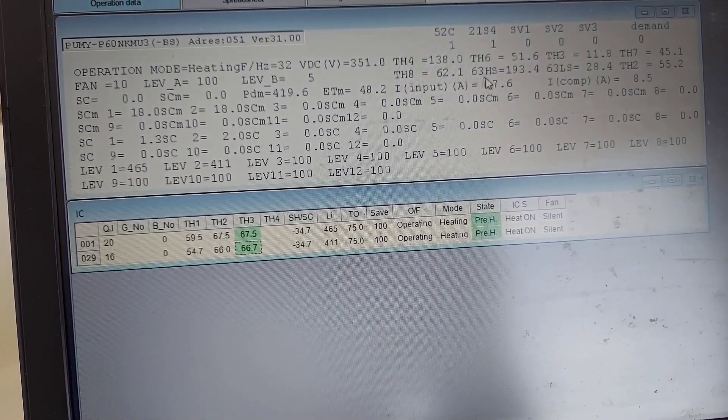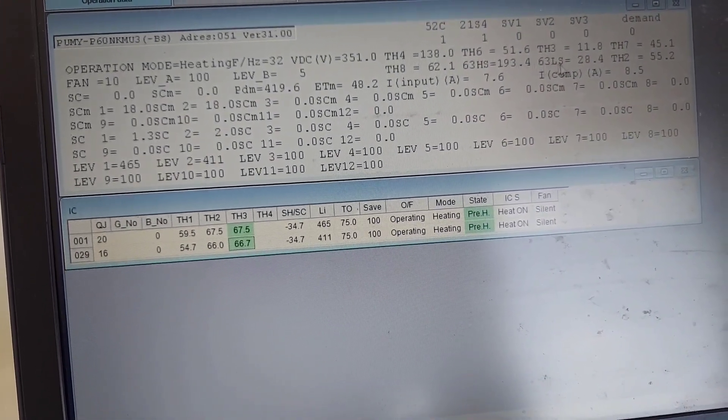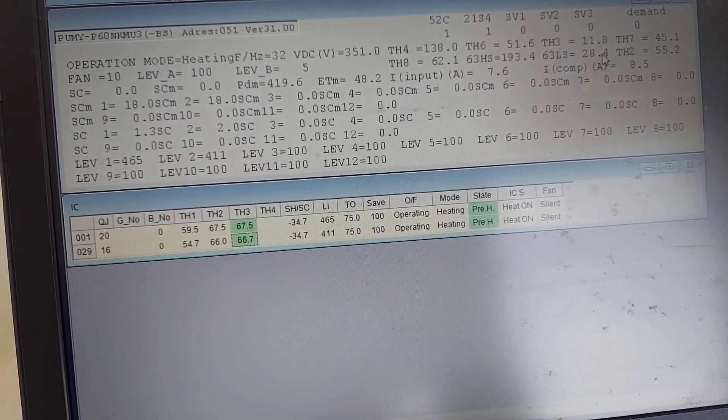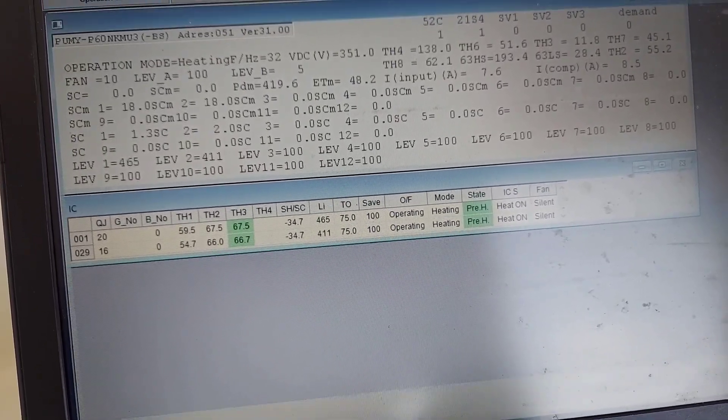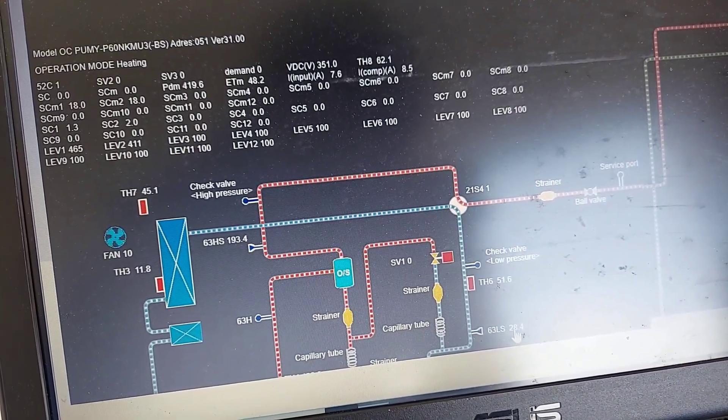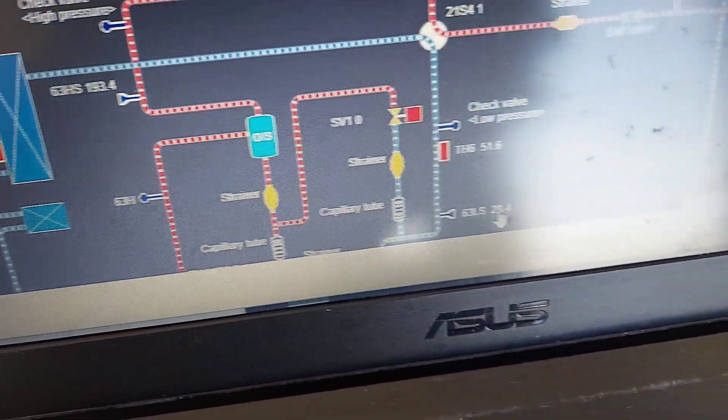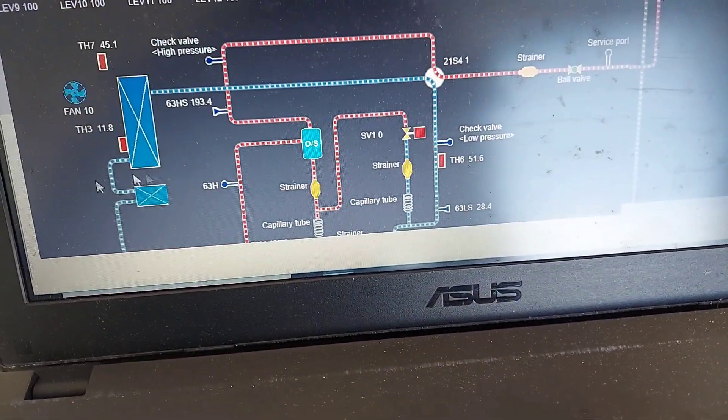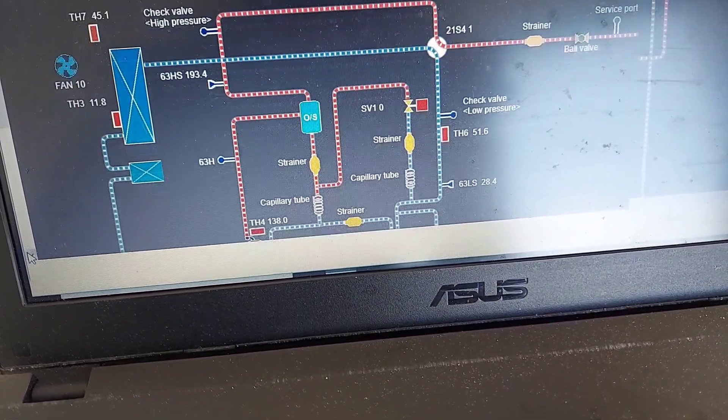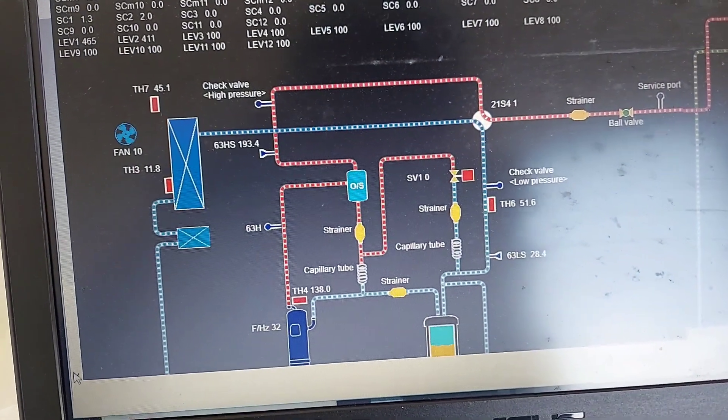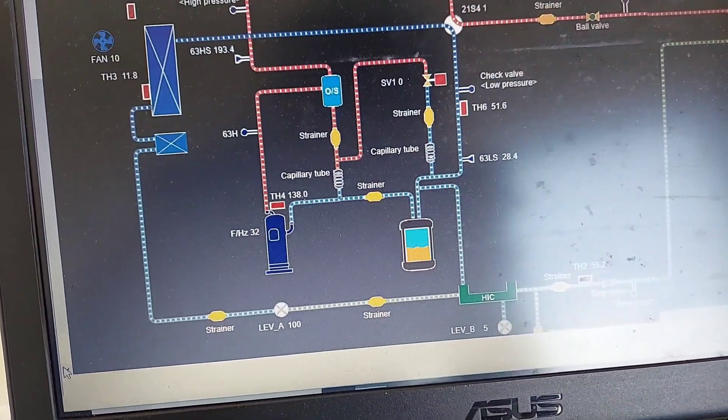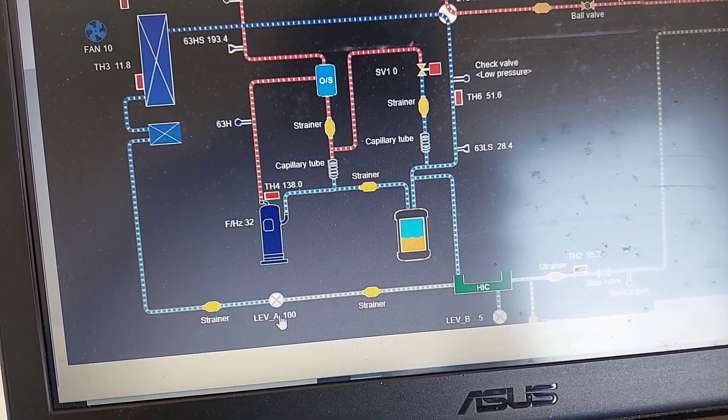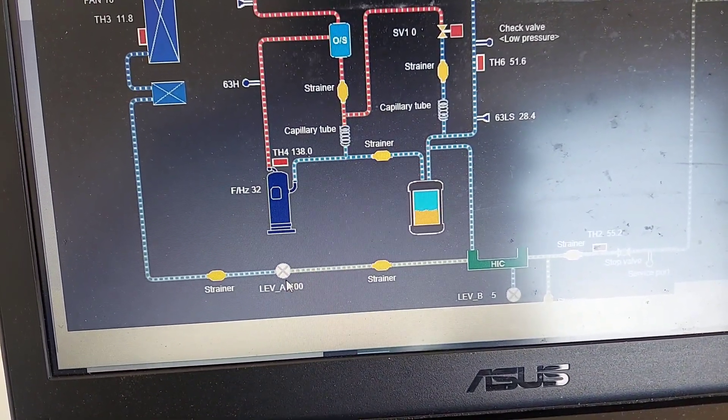Well let's see what happens, let's see what transcends. Head pressure is only at 193, oh my low pressure is at 28 now. Wow, let's go back to the diagram. Yeah, 28C, 28 psi low side. So yeah, I think that my initial hunch based on experience is correct.